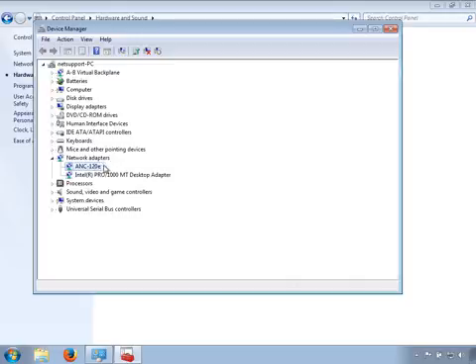Check the Device Manager window. Now the ANC120E should appear as a new network adapter under the Network Adapter list. The driver package creates a new Ethernet network adapter which is used to communicate with the device over the USB port. The default IP address of the device is set to 192.168.137.2. The first time the device is used, it is required to configure the network adapter created by the driver to use a static IP address in order to access the ANC120E web configuration interface.